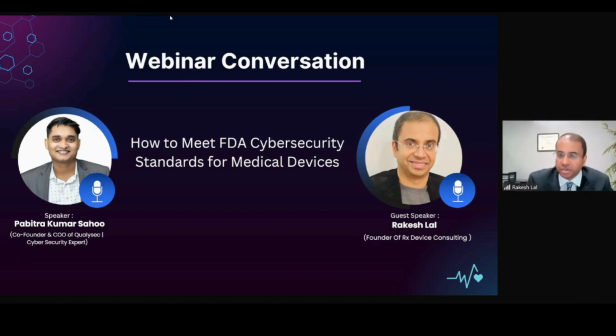Yes. So cybersecurity is a growing concern for medical devices and FDA these days. A lot of medical devices have software and have cybersecurity issues that need to be managed. So FDA requires manufacturers of devices that have software and are at risk for cybersecurity threats to address these risks, implement the appropriate controls, and provide documentation demonstrating that you have these controls in place. This includes thorough, comprehensive threat modeling and identification of vulnerabilities and threats, development of risk assessments, implementation of strong access controls and other cybersecurity mitigations, and also performing comprehensive security testing, which would likely include pen testing, and having a robust response plan for any incidents that might occur.